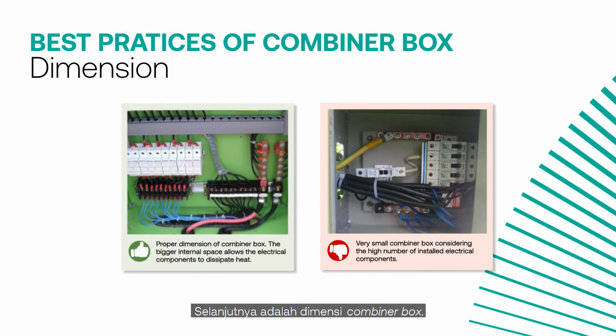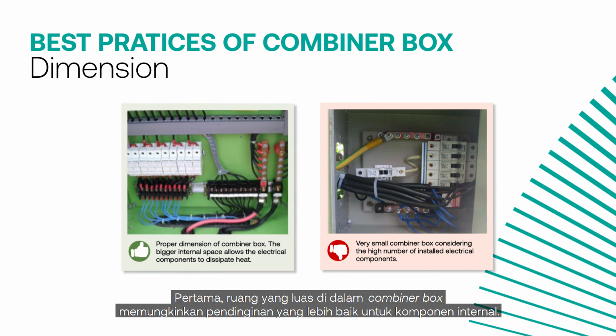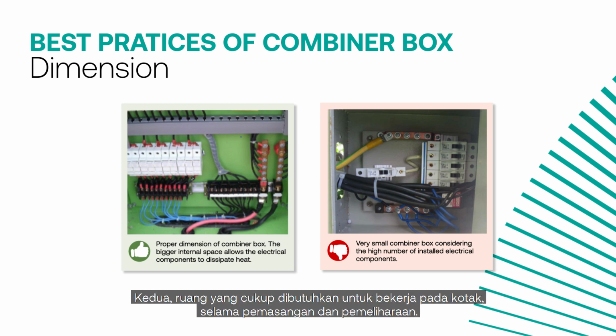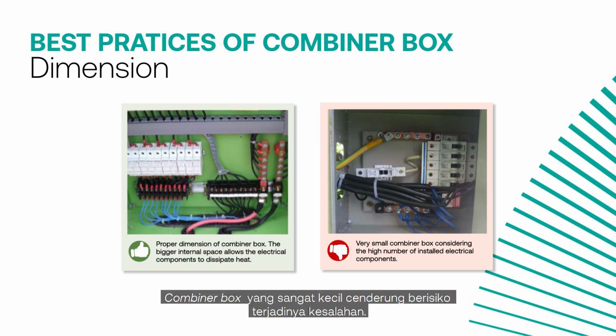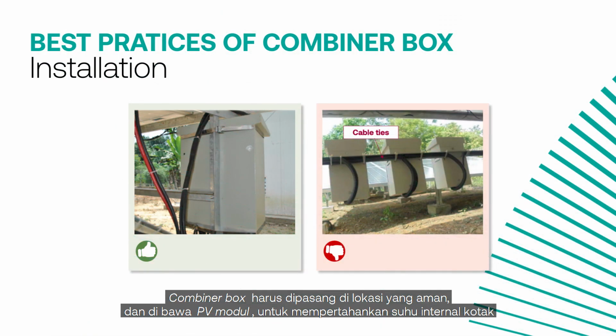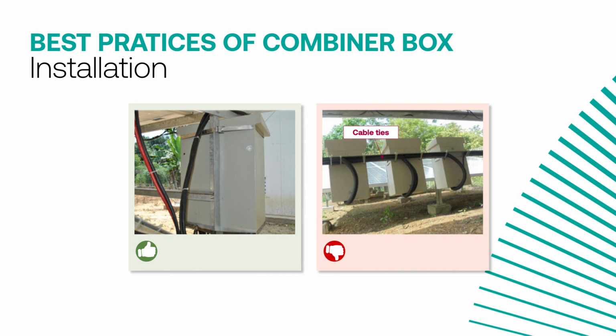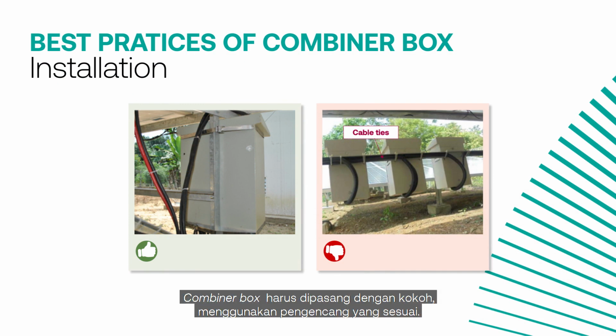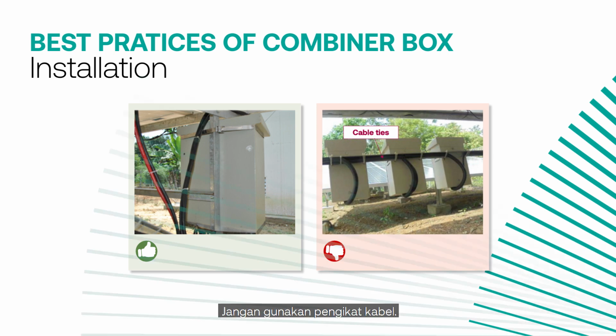Next is the combiner box dimension. The dimension should not be too small. Why? First, a spacious area inside the combiner box provides better cooling for the internal components. Second, sufficient space is needed to work on the box during installation and maintenance. A very small combiner box is prone to unexpected mistakes. The combiner box must be installed in a safe location and below the PV modules to maintain the desired internal temperature of the box. The combiner box must be fixed and mounted firmly using suitable fasteners. Do not use cable ties.